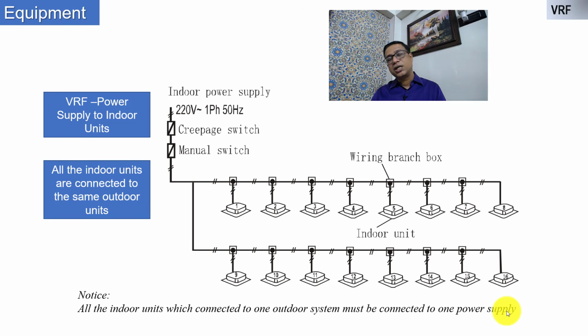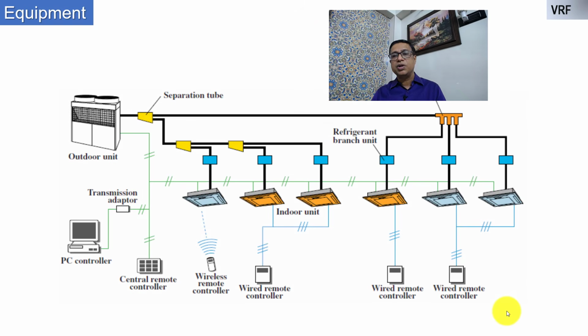So how it works, as I said, you have one outdoor unit connected to multiple indoor units, and the indoor units can be the same or different. It can be vertical, high wall, cassette, or one-way cassette. You can combine these, and that's why it is getting more and more popular. This is a smart system connected with an electronic expansion valve, which works on the load requirement of that space. So it automatically gives a signal back, and if there is no load in the room, it automatically operates accordingly.